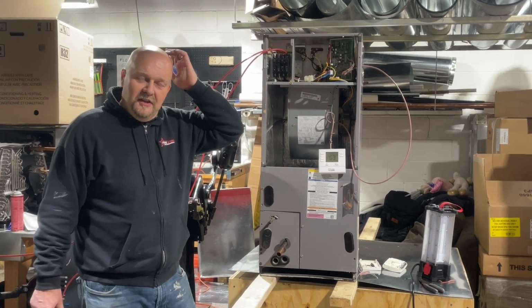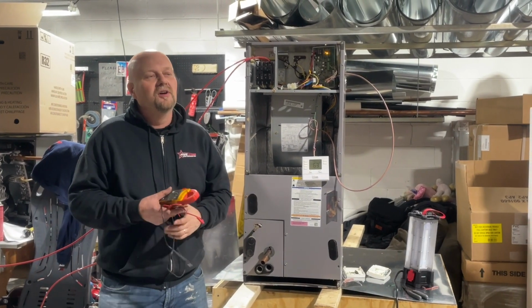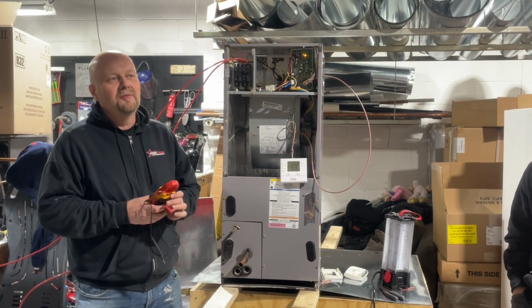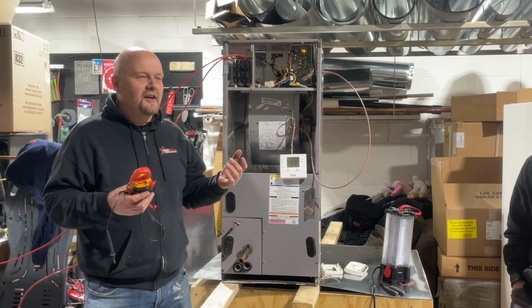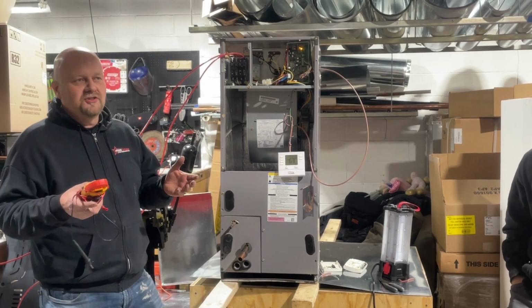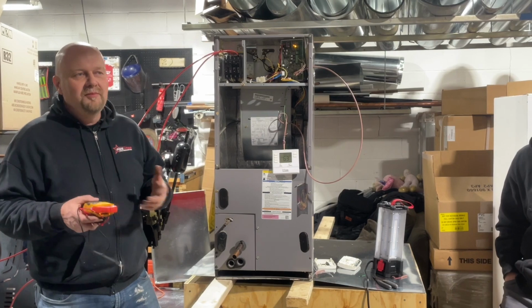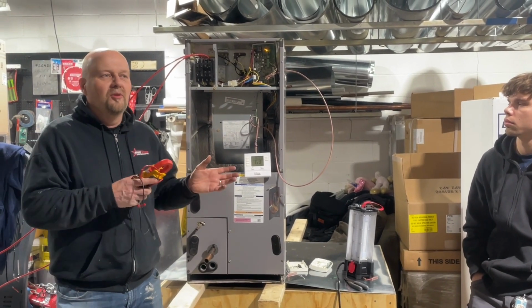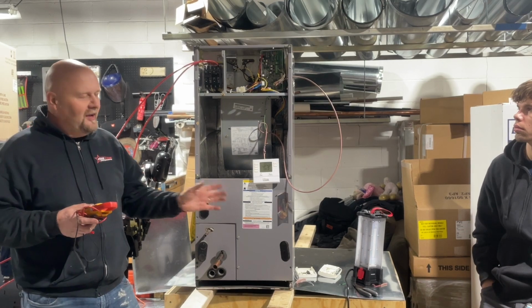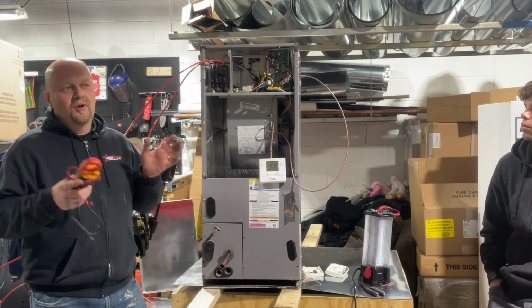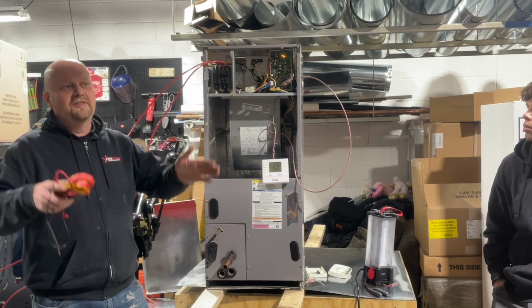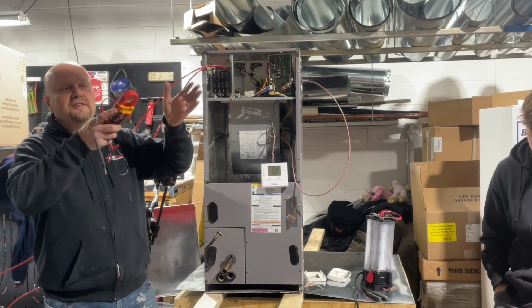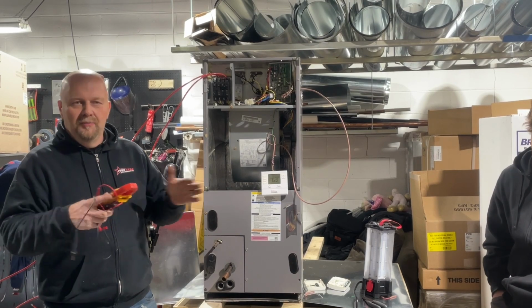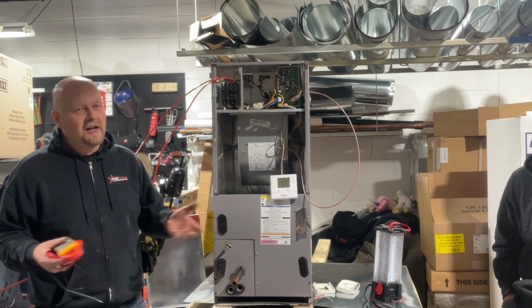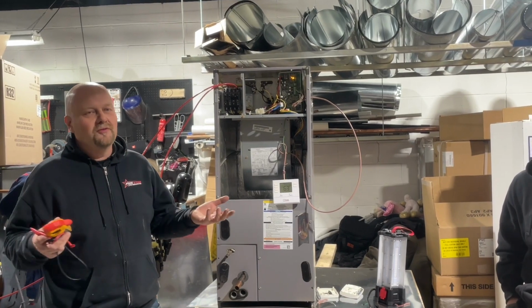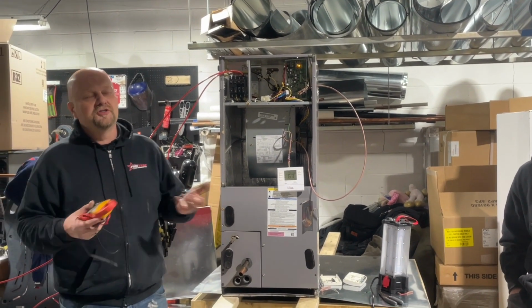Okay, that's a function of what's out there, right? Gas-fired furnaces have been out there for such a long time, and traditionally no one cared about attaching heat pumps to them. Now there is a way to install a furnace and use it in the same way, but you have to do something that's not traditional. You have to put the evaporator coil under the furnace. Majority of the time, when you walk into people's homes, you have the furnace and then the evaporator coil, or the air conditioning section, sits on top of it. We could potentially reverse it and put the coil on the bottom and suck through the coil. There's no reason not to. It's set up the same way for us to suck through it as for us to blow through it, but we traditionally don't do it.